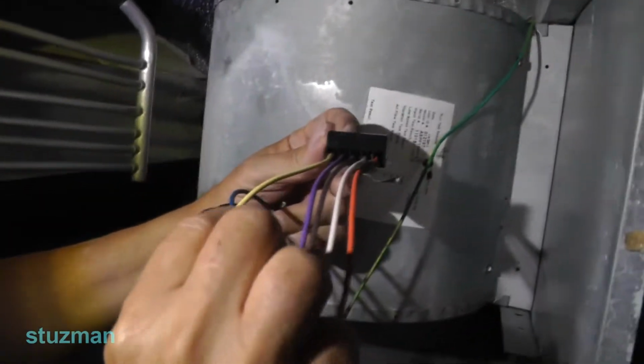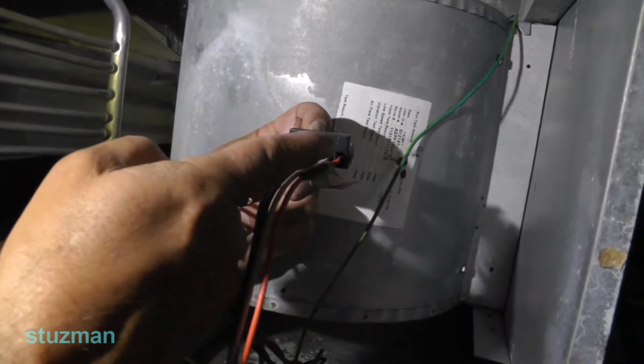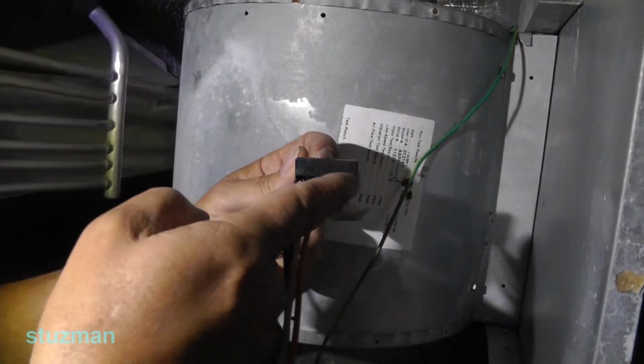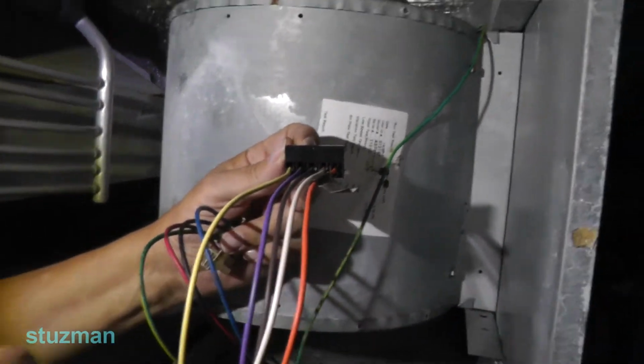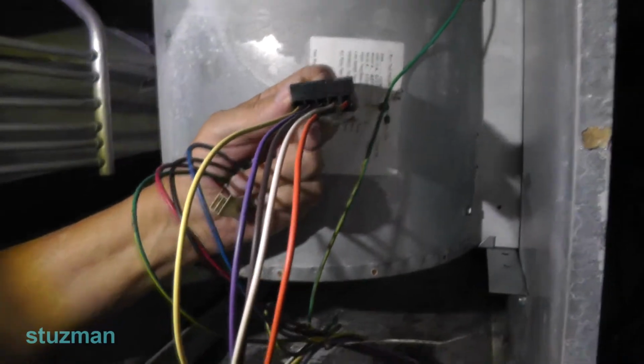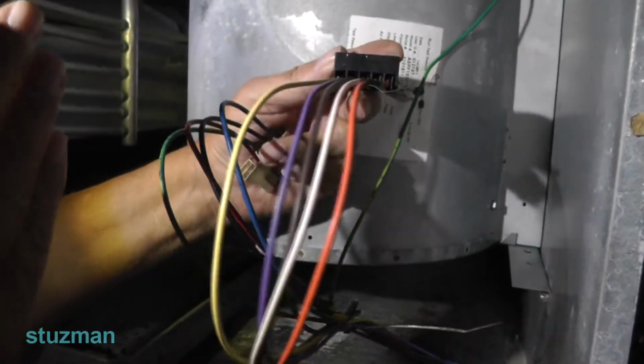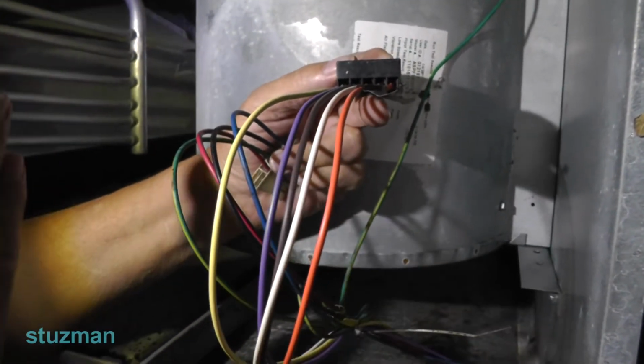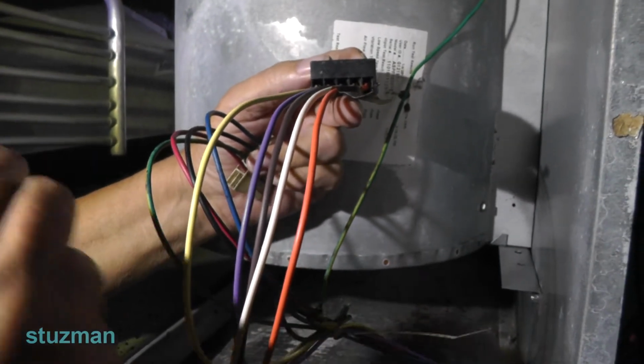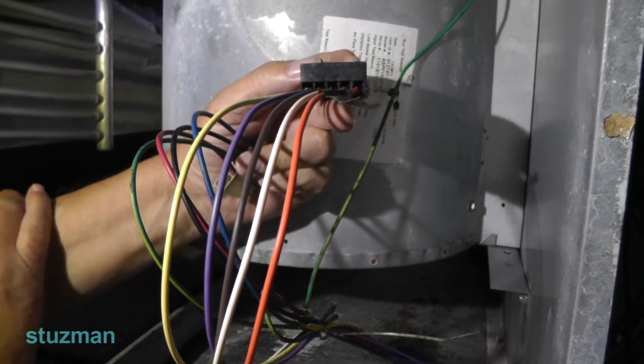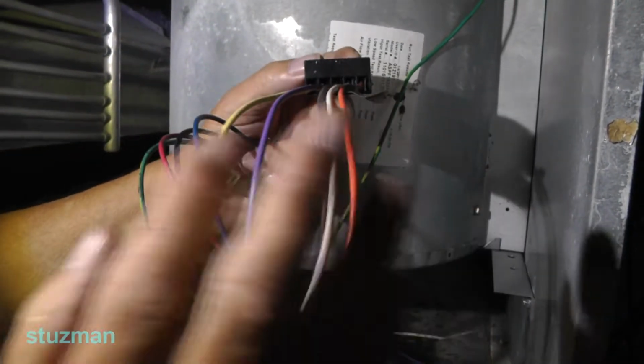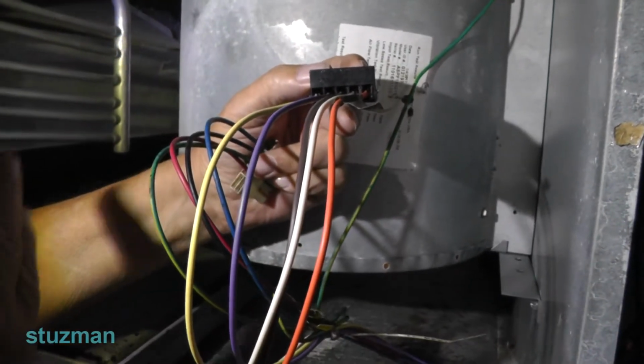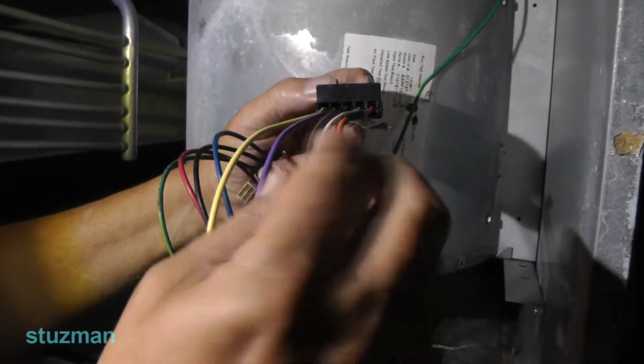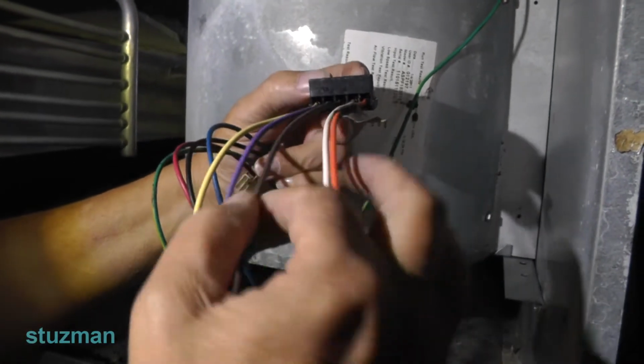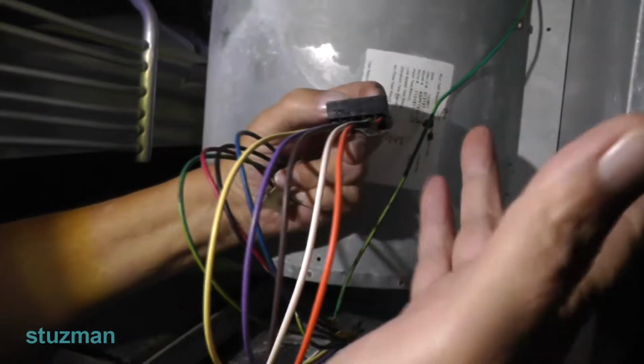So the manufacturer can program any one of these, or multiple of these. For example, if you're on the cooling cycle, you're going to need more speed for the airflow when you're in cooling mode. So he can program one of these taps for a particular torque setting, which will give you a particular fan speed setting for cooling. Now when you go to heat, you'll be on another tap.